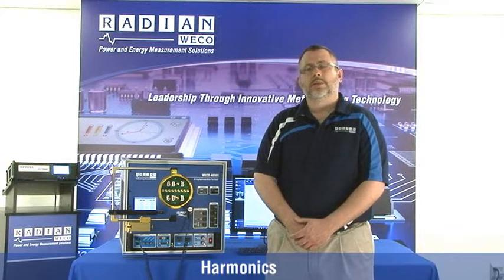The challenge is that a phantom load test is typically pure sinusoidal, and customer load testing, although under real-world harmonic conditions, cannot be reproduced reliably because you are at the mercy of changing load conditions from moment to moment. This leaves us with a utility customer that has lost confidence their meter is measuring energy properly under real-world conditions. So how can we win our customers' confidence back?